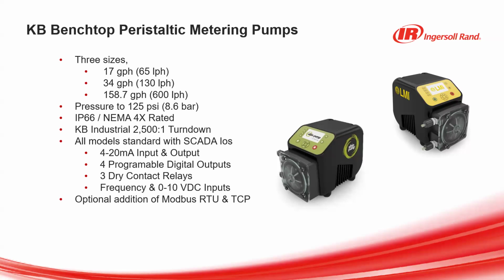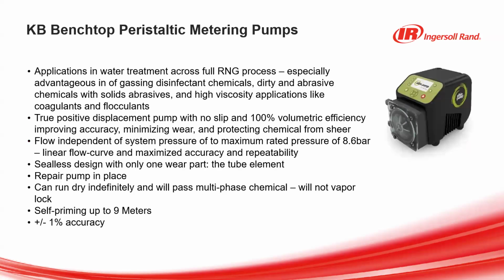It's a true positive displacement pump, meaning you're not going to have slip through the pump, and you're going to get accuracy and reliability throughout the entire lifespan of the pump in balancing water chemistry. All models of the peristaltic metering pumps come standard with SCADA connectivity options. That includes 4 to 20 milliamp inputs and outputs for integration into SCADA systems, 4 digital outputs, 3 contact relays, as well as frequency and 0 to 10 inputs.